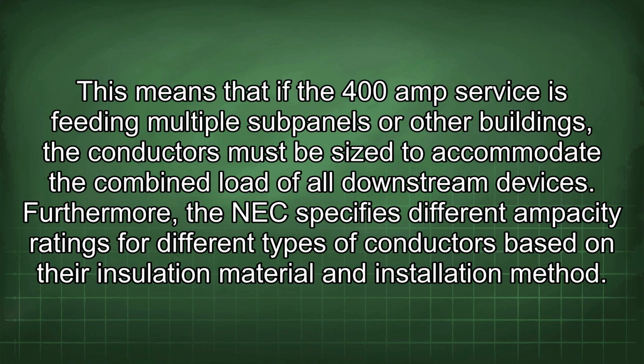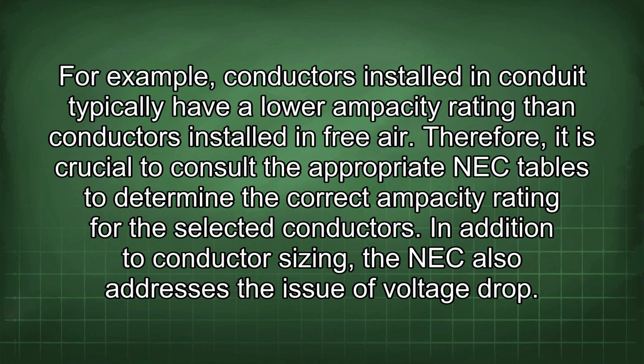Furthermore, the NEC specifies different ampacity ratings for different types of conductors based on their insulation material and installation method. For example, conductors installed in conduit typically have a lower ampacity rating than conductors installed in free air. Therefore, it is crucial to consult the appropriate NEC tables to determine the correct ampacity rating for the selected conductors.